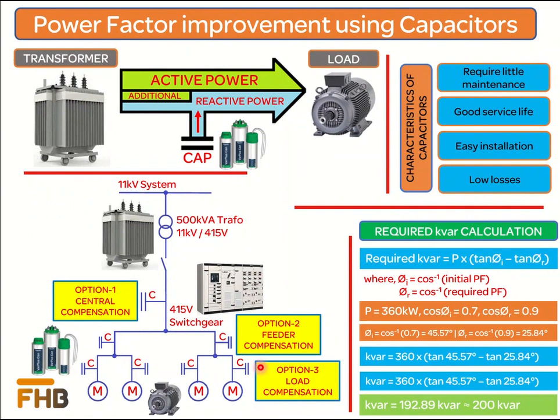The value of capacitor banks required for a power system is measured in kVAr. Assuming a 360 kW connected load where we need to improve the power factor from 0.7 to 0.9, applying the formula shows that we need to install capacitor banks of 200 kVAr.